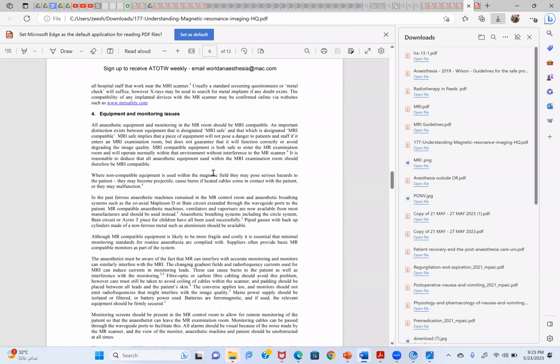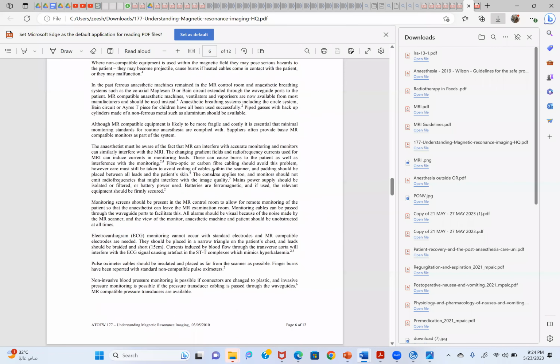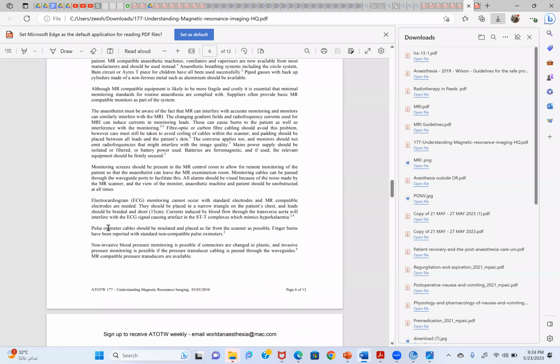Yes, maybe the endotracheal tube does not have any metal, but there is a metal in one of the parts of the endotracheal tube. Do you know what is that part? That is the balloon. Okay. There is a spring over there. So you will see that they just put a tape over it. I never understood how that is not creating a problem, but that's usually what we do. Okay, they just put a tape over it. And there are incidents of burn. There was one case report in our hospital where there was a burn with the pulse oximeter. The normal pulse oximeter was there and there was a burn.